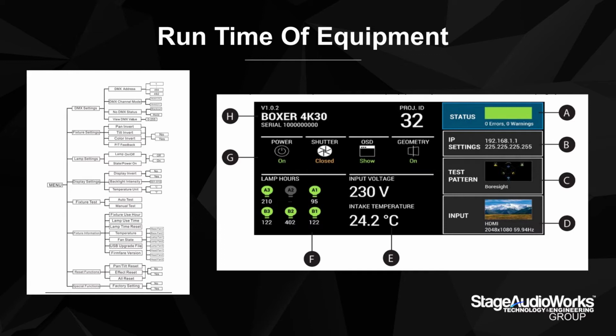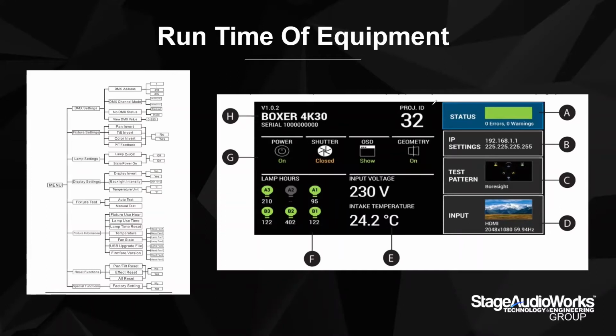From a service interval perspective, it depends on the environment and what resources you have. If it's a house of worship with someone who manages the equipment, they can do general maintenance - at least once a quarter if it's a really dusty environment, or every 6 months to check filters and dust buildup in a rack if it's a nice, air conditioned and filtered space. So I'd say 3 months for a dusty environment and 6 months for an okay-ish environment from a dust perspective.